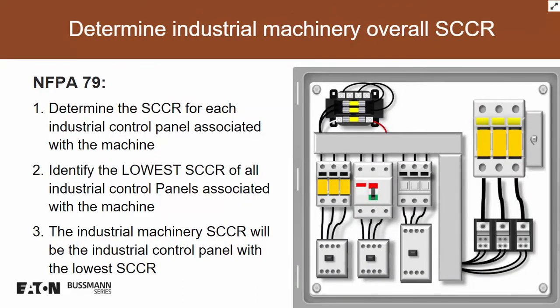So how do we deal with that? What are the situations that we could be faced with? Well, just a recap of what Joe covered, we can apply essentially the training that Joe just elaborated on for determining the overall short circuit current rating of a panel. We can apply that to machinery. For example, you can determine the short circuit current rating for each control panel associated within the machine if you have multiple control panels. Then you look for the lowest short circuit current rating of all the panels that are provided with the machine, and then the industrial machinery short circuit current rating, the short circuit current rating for the entire machine, becomes the industrial control panel with the lowest SCCR. This is basically the weakest link method. So as Joe described it for you, when you're working on an individual panel, use the same method when you're talking about determining the SCCR for machinery.